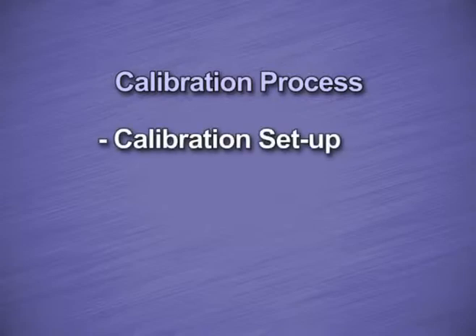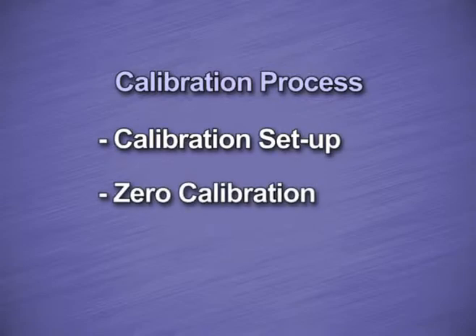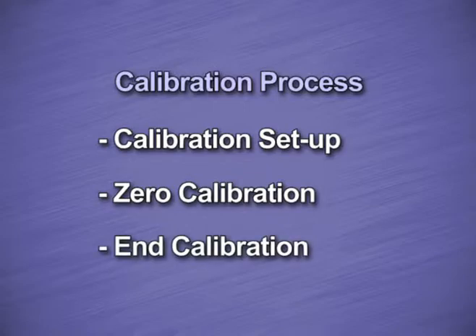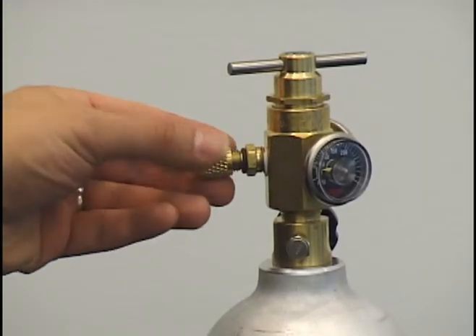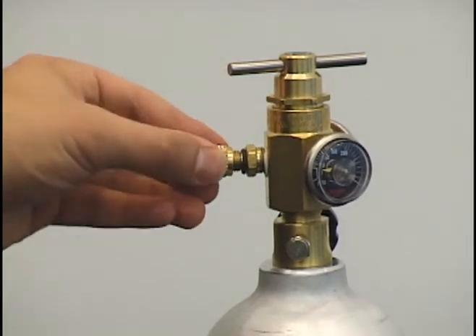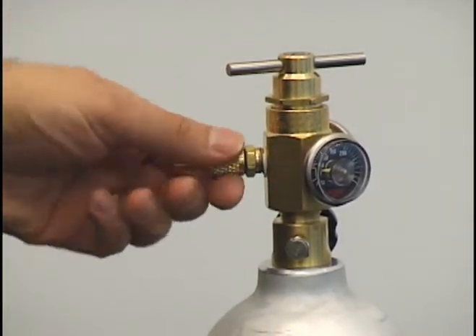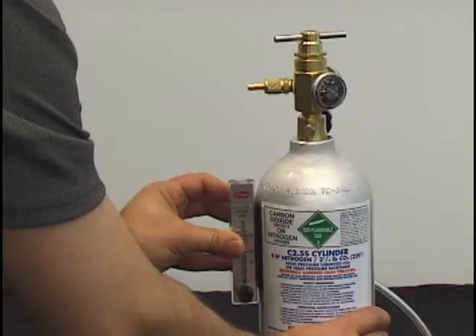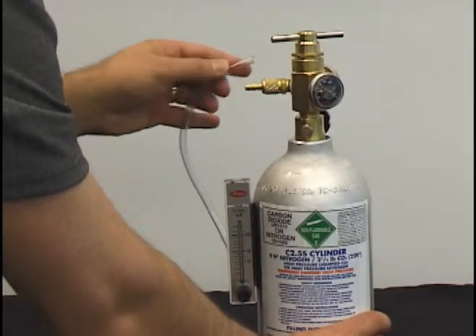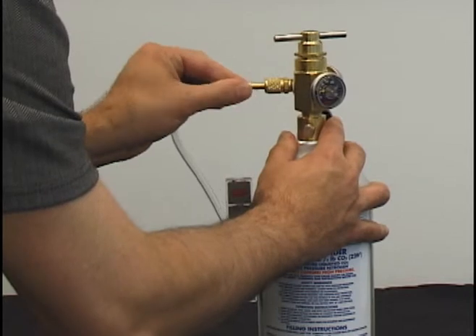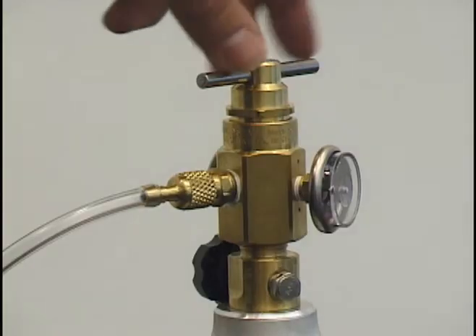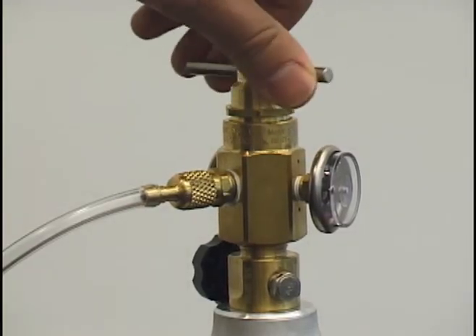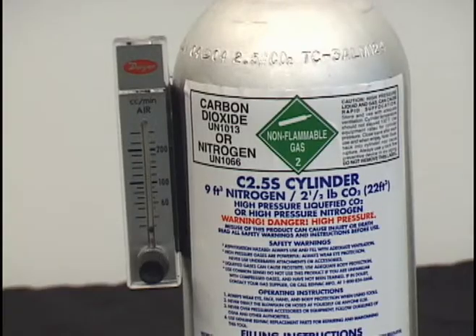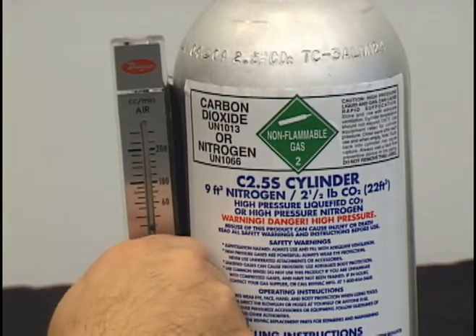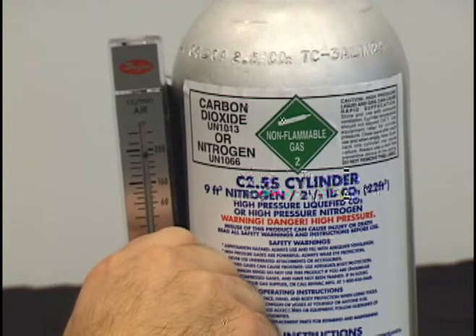The procedure consists of 3 easy steps: calibration setup, initiating zero calibration, and end calibration. Step 1. Calibration setup. First, connect the cone tip fitting to the gas bottle regulator. Then connect the 1/4-inch Tygon tubing from the flow meter to the cone tip. Next, turn on the regulator and set to approximately 25 psi. Keeping the flow meter vertical, adjust the flow meter to 200 cc's per minute flow rate.